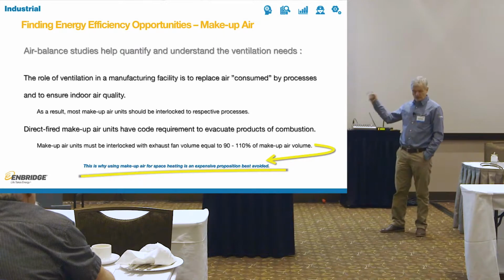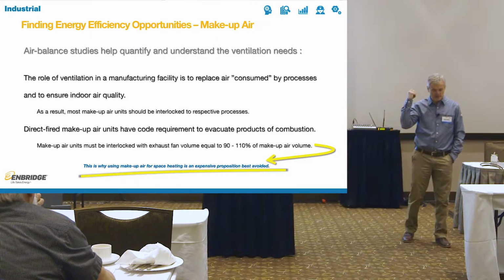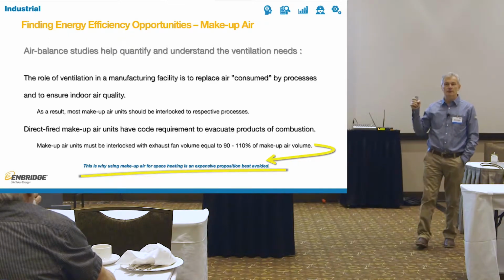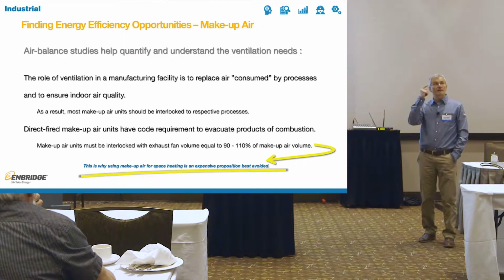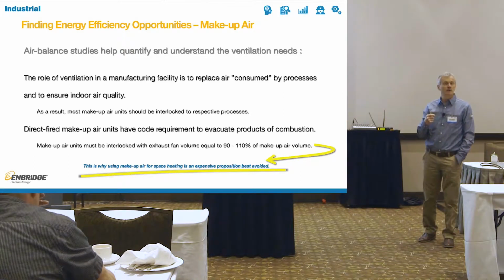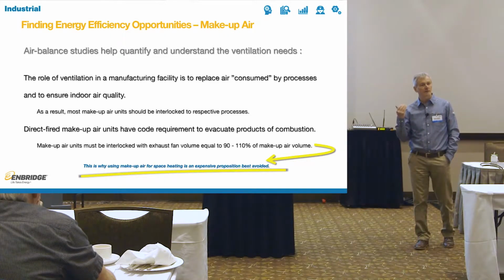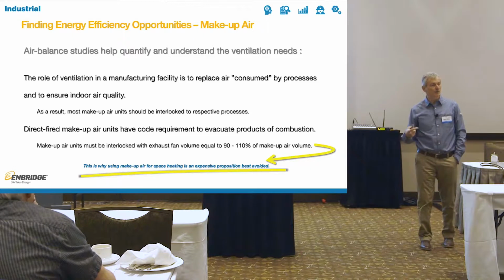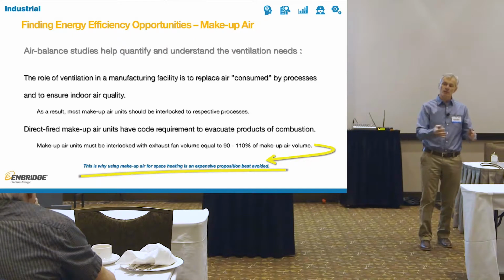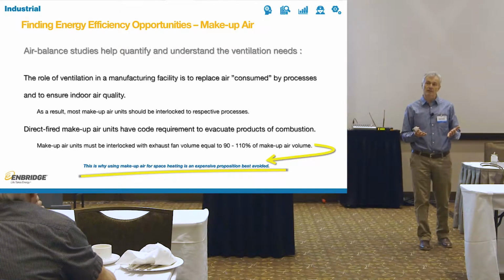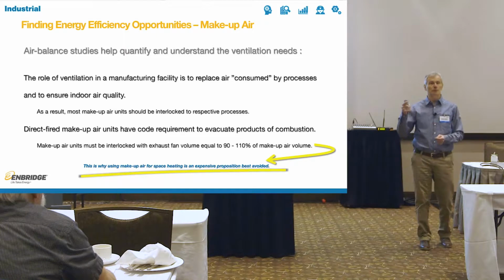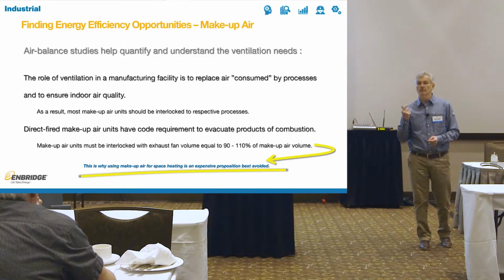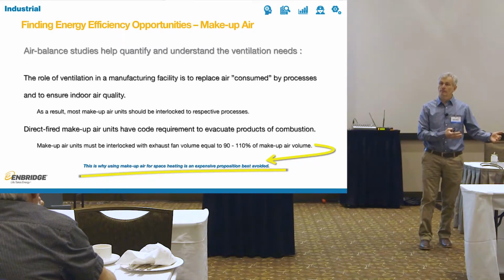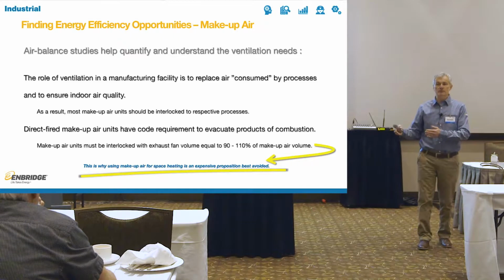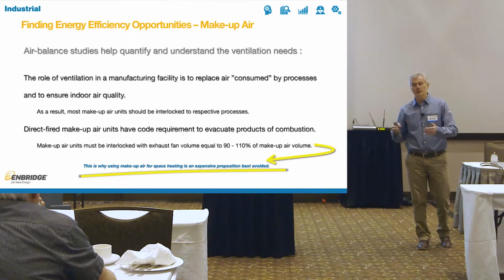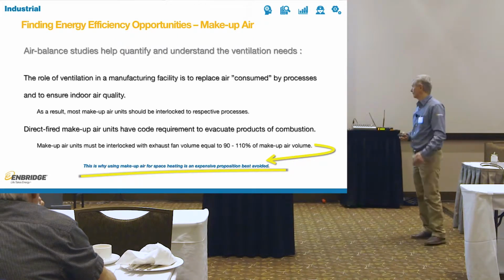So let's take a look. This is a reminder for me. This reason of interlocking, if you really do it properly, is why makeup air should not be used for space heating. As I said, here you get away with 400 CFM of fresh air, which means that you have to evacuate about 400 CFM of air. And then you can use the baseboard heating or some other ways of heating to actually keep us warm. So keeping the space warm, plus 400 CFM of air, is not bad. But imagine how much heat you would need in here if you now put 40,000 CFM of air blasting through this place. Either that or it would be really cold air. So the more makeup air you put into the facility, the more heat you have to provide. So heating your facility with makeup air is a bad idea. Bad. Expensive.